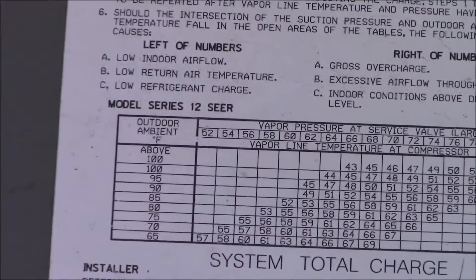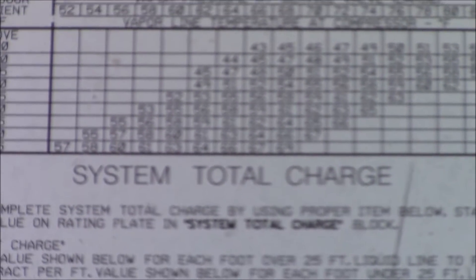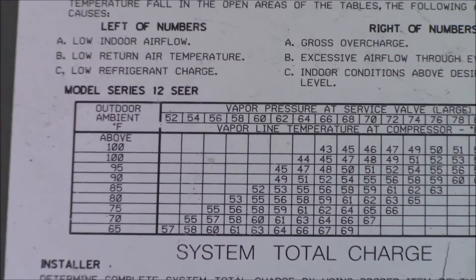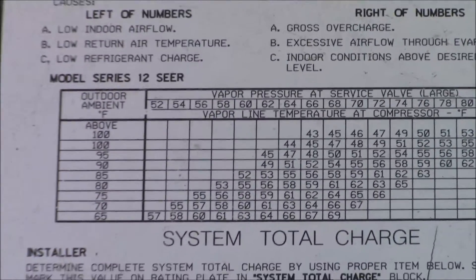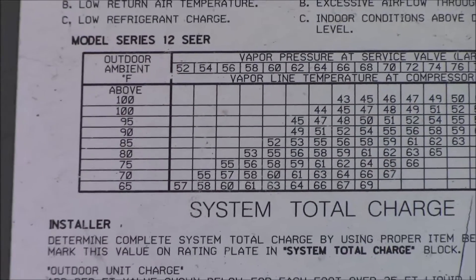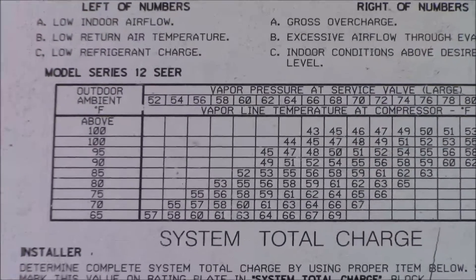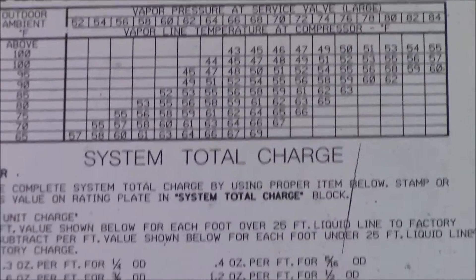When you look at it: outdoor ambient temperature — the temperature outside. You take that temperature at the condenser air inlet. Vapor pressure at service valve — the large one — that's your suction line: 52, 54, 60, 62 and so on. Vapor line temperature at the compressor. So compare ambient to your suction pressure. If the outdoor ambient temperature is, say, 85 degrees and we go to 62 psig, you're looking for about 53 degrees suction line. You get that 53-degree suction line and by the manufacturer's chart it's working correctly.